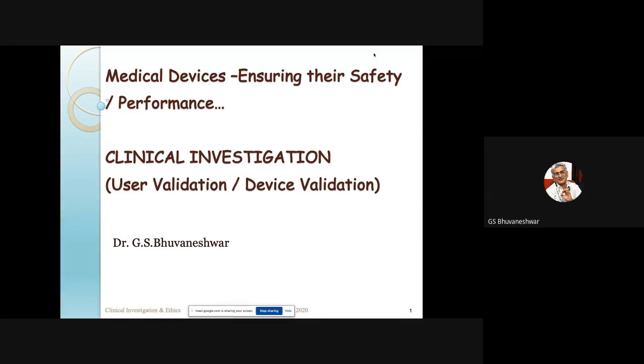So primarily, as I said, this is an introduction to what is involved in a clinical investigation. There are a number of terms. Basically, they're also called user validation or device validation. I would say clinical investigation is a part of user validation or device validation, but there could be other aspects of validation more than clinical investigation. Clinical investigation is one very important part of final validation of a device.